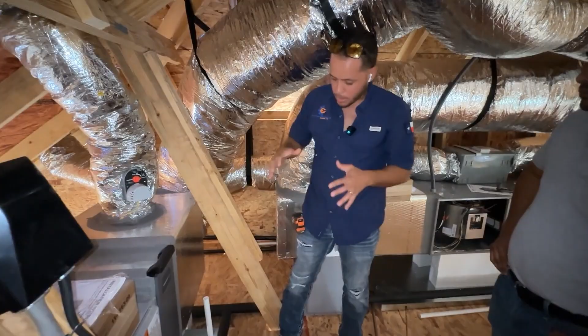So the way that they are connected is in the inner liner. You put duct seal in it, you put the duct in the collar, then you strap it with a zip tie, then you roll insulation inside with the outer liner, and then you put another zip tie in it. In order to have a good seal, then you have to coat it with the duct sealant or mastic. That's something that is required here in Austin as well. That's the way to do it here.